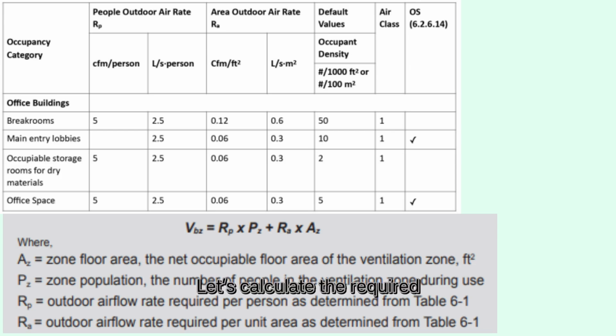Let's calculate the required outdoor air for an office and a break room using ASHRAE Standard 62.1. The office area is 43,000 square feet with 225 people. The break room area is 2,000 square feet. From Table 6.1, the office has RP equal to 5 CFM per person and RA equal to 0.06 CFM per square foot. The break room has RA equal to 0.12 CFM per square foot.